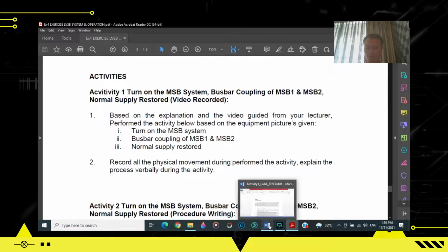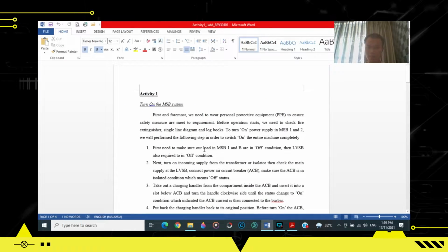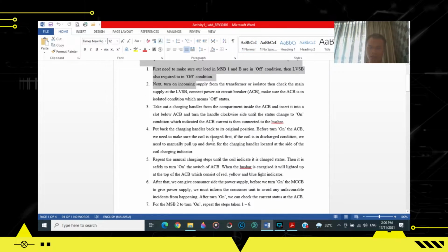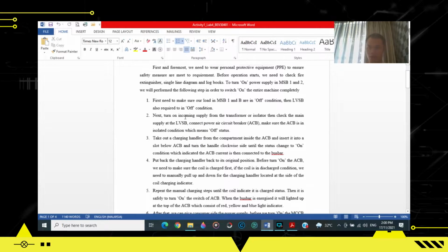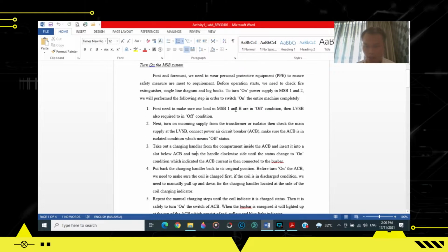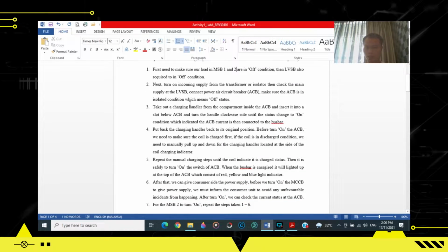Based on the video given by the lecturers in the electrical lab, power engineering lab, I'm going to define that turning on the MSB systems has 7 steps. Well, first we need to make sure that our load MSP1 and 2 are in off conditions. Then the LVSB is also required to be in off conditions.